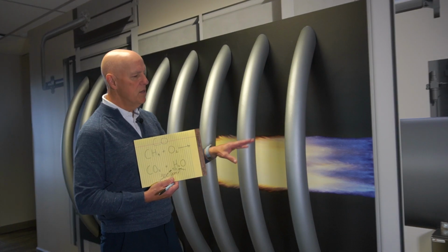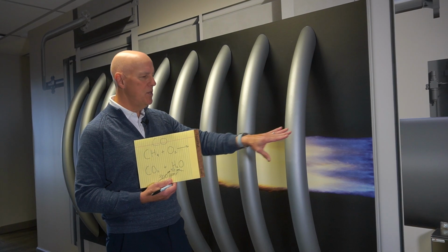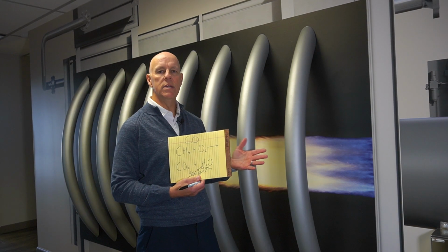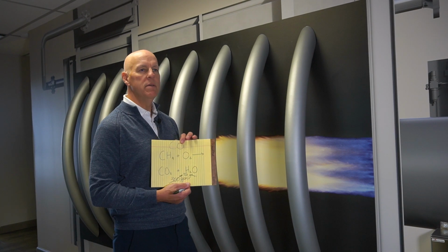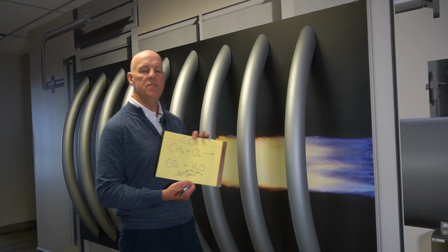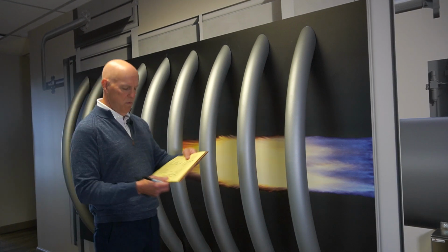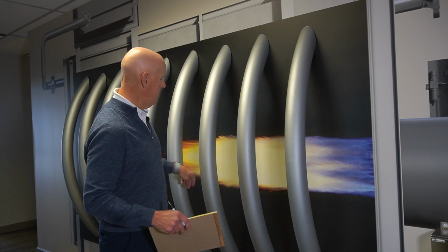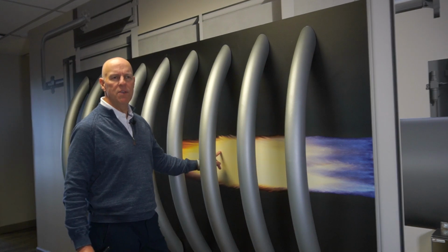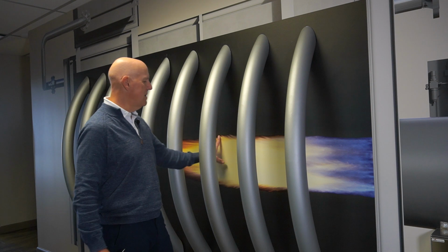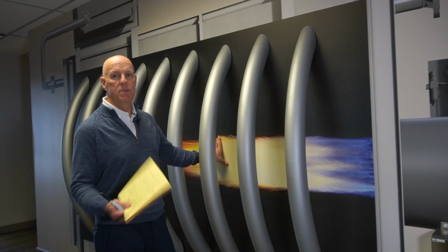So if you've got a good burner, good air to fuel ratio, your gas tips are clean, and you're firing at normal rates, everybody's happy, you're making less than 50 ppmv of CO. So how is that if I'm maybe at 2000 ppm CO here, but coming out of the stack, I'm at less than 50?